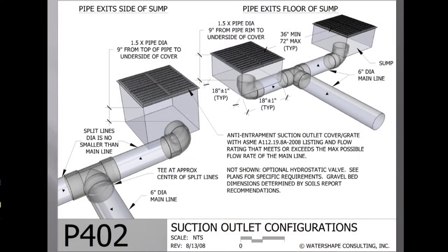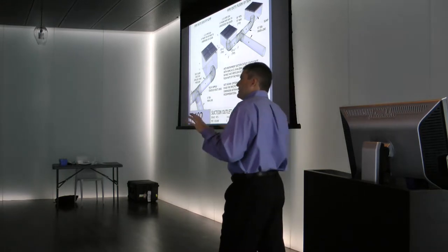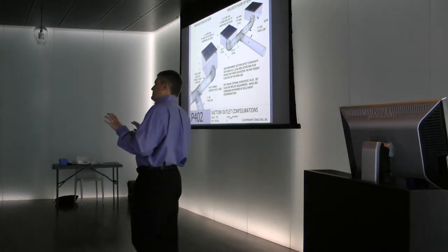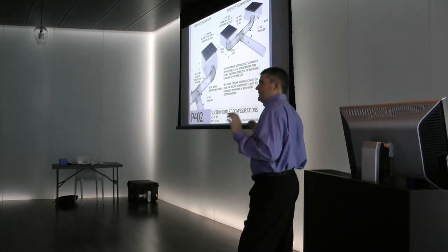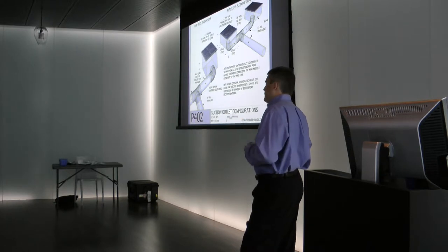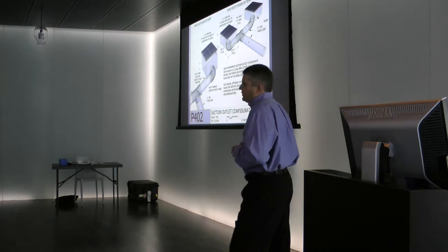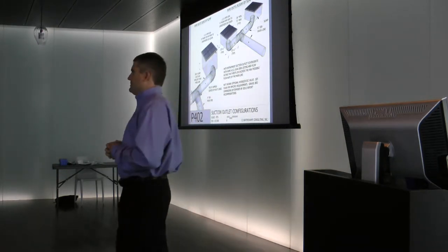In fact, the force that you're limited to in terms of pushing off is 15 pounds. That 15-pound force actually came from some studies in Europe regarding the panic hardware on doors. They wanted to make sure that children could get out of a burning building, and after they did these studies, that was the force determined: you needed to be able to push a door with no more than 15 pounds. So they just took that same rule and applied it here in this standard.